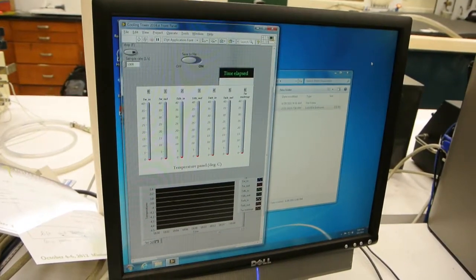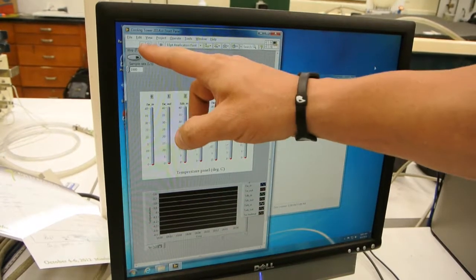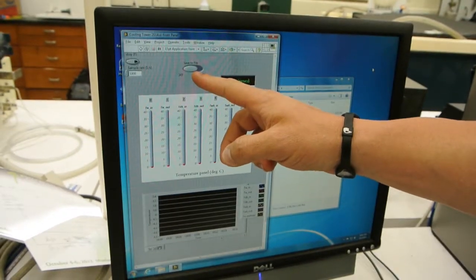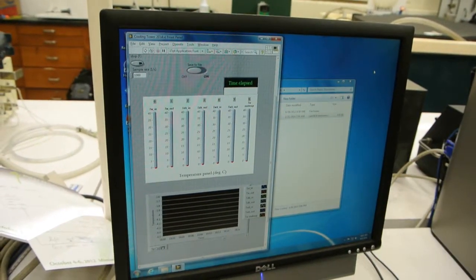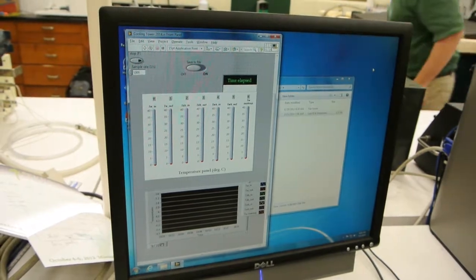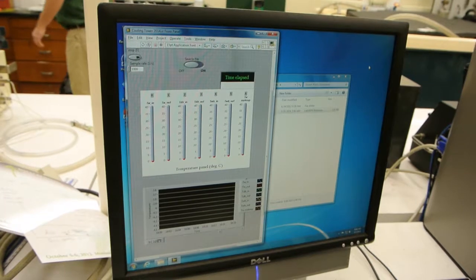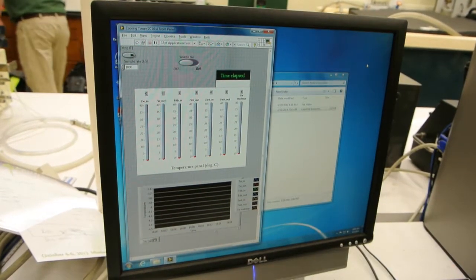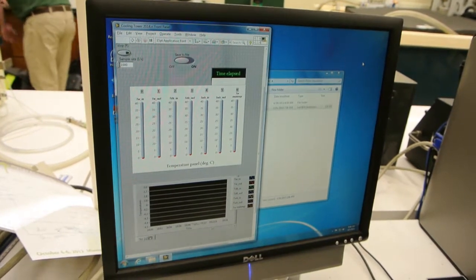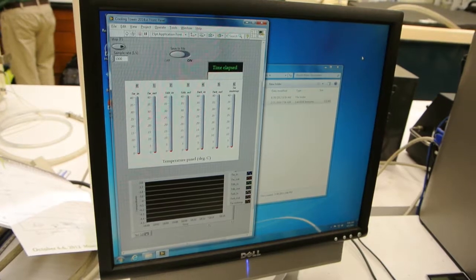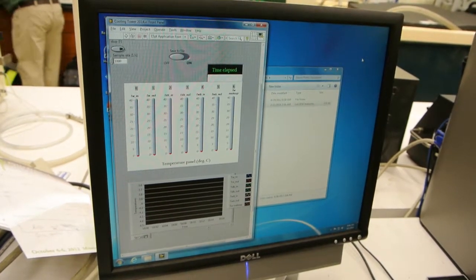This is the LabVIEW program. You will start this by hitting the run button. Record all temperatures by flipping the data save switch on the LabVIEW control panel for 10 seconds. Record the total time shown on the LabVIEW interface. This value will be used to determine the average mass flow rate of the makeup water during the experiment in these tables right here. Record the pressure of the orifice differential after the airflow has reached steady state.